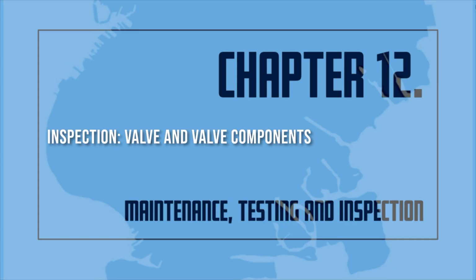All alarm valves and their associated strainers, filters, and restricted orifices shall be inspected internally every 5 years unless tests indicate a greater frequency is necessary. Exterior valves shall be externally inspected monthly to ensure that they are free from physical damage, the valve seat is not leaking, all trim valves are in the appropriate open or closed position, and electrical components are in service. Exterior dry pipe valves shall be externally inspected monthly to ensure that they are free from physical damage, the intermediate chamber is not leaking, all trim valves are in the appropriate open or closed position, and electrical components are in service. Check valves shall be inspected internally every 5 years to verify that all components operate correctly, move freely, and are in good condition.